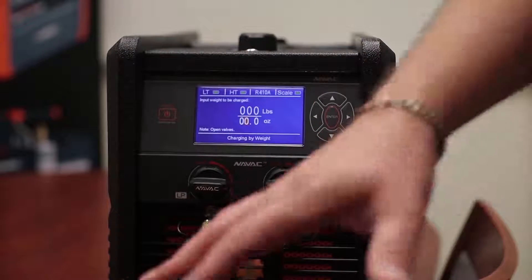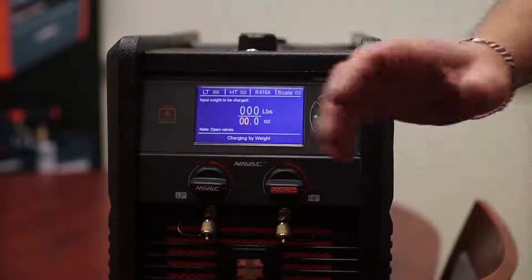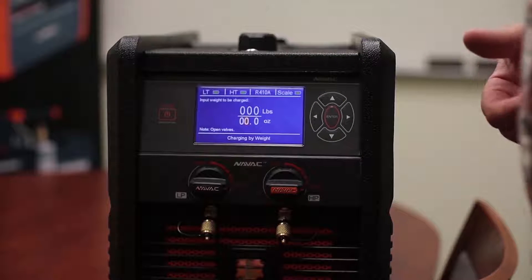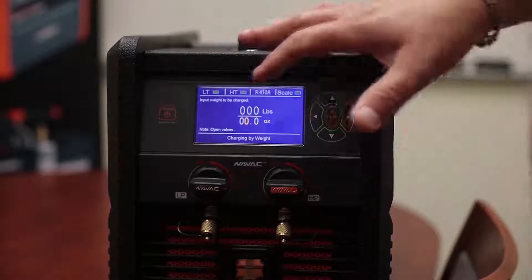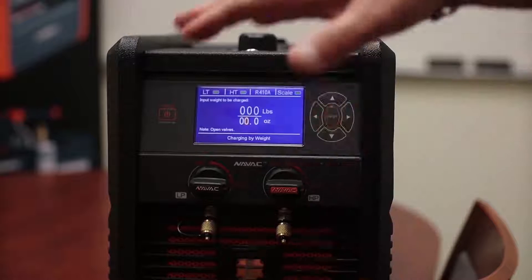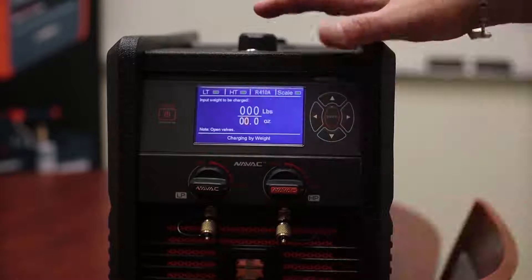Once you've got everything connected and the machine is weighing the tank, do not touch the tank. We have a habit of, oh, it's moving slow, let me juggle the tank. Well, this is very sensitive because we're talking about critical charge. So it thinks that's how much more has been added to the system and it's going to throw off your entire charge. So once you're set, don't touch the tank anymore.